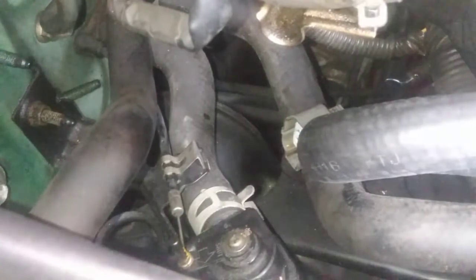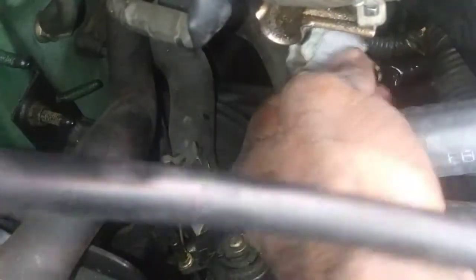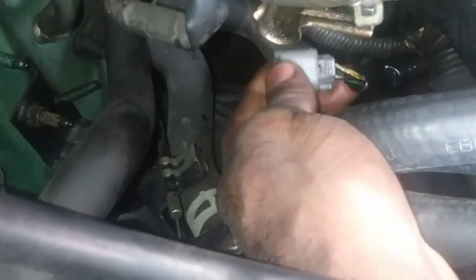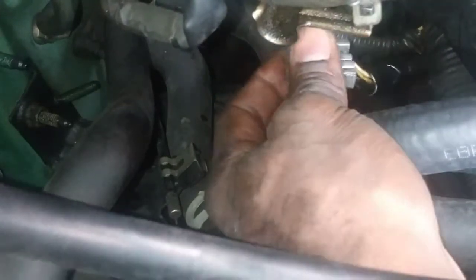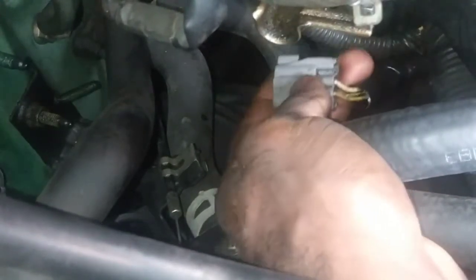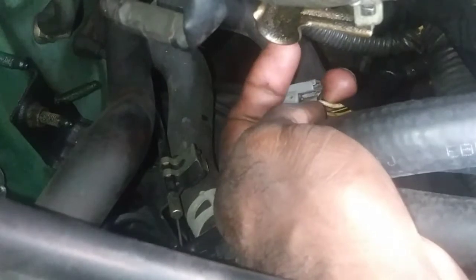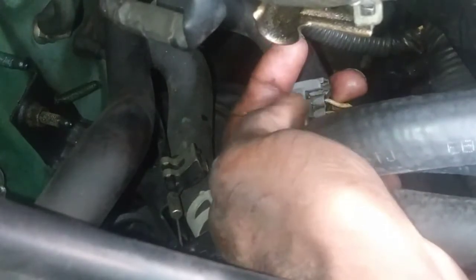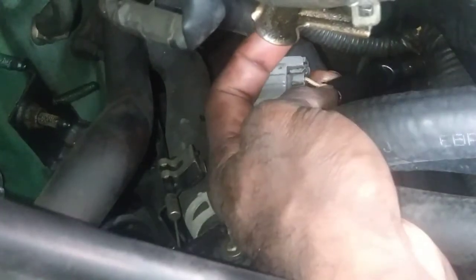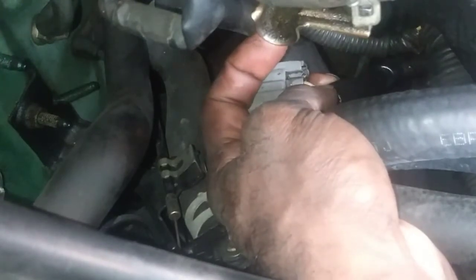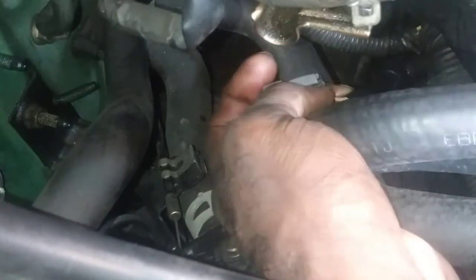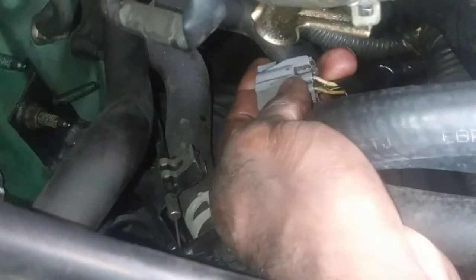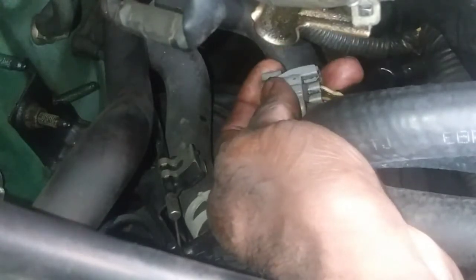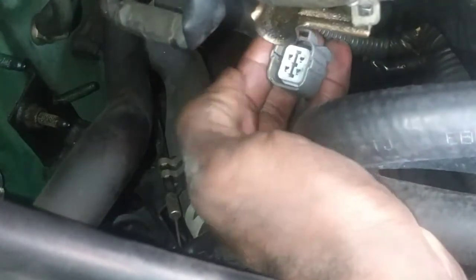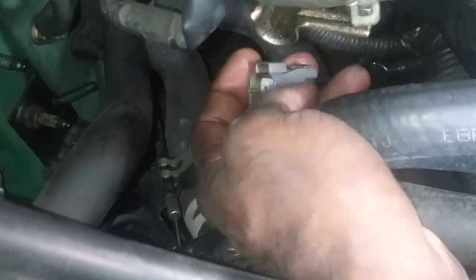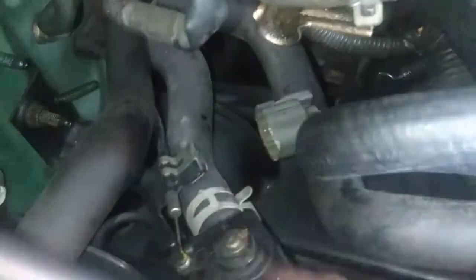So what we're going to do is check the value on the white wire, which is our signal wire, and see if we have that 1.2725 or whatever value, that's our bias voltage there. When this bias voltage, when everything is working appropriately like it's supposed to, that resistor from that ground circuit is going to drop that voltage value, which it isn't. So we're either missing one or the other, or the sensor is simply defective, if you follow me.